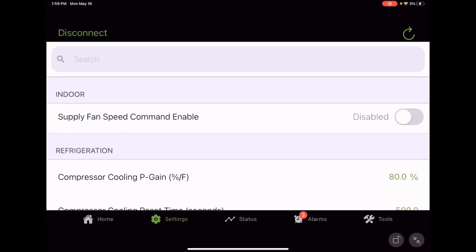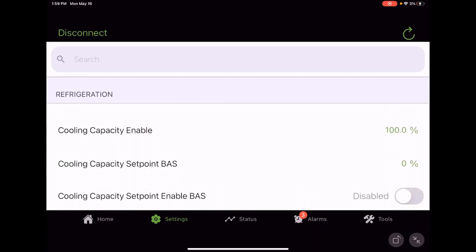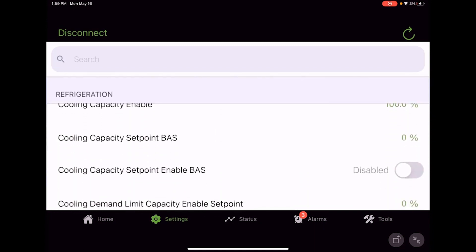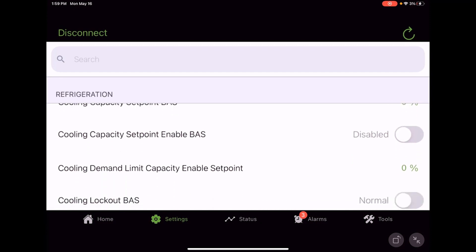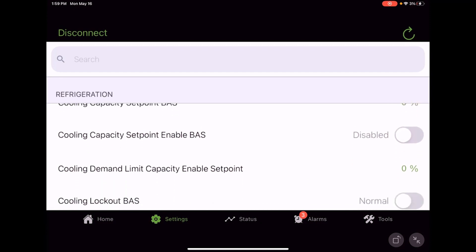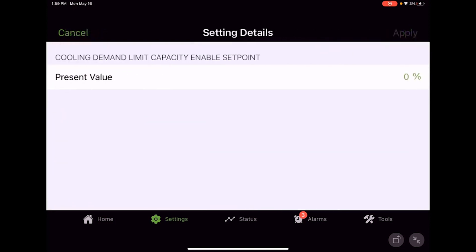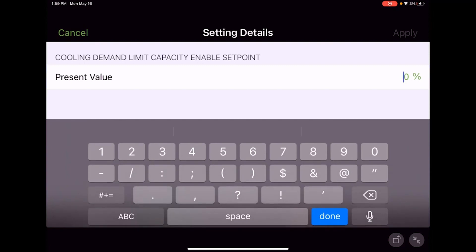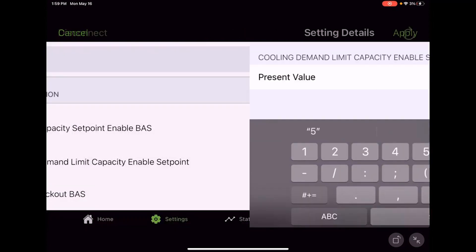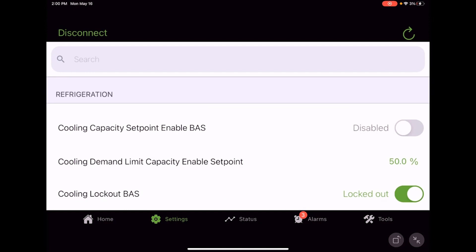We've got other settings here. We've got some things that have to do with cooling capacity demand limit. So if demand limit is triggered, we may want to demand limit that unit 50%, so we'll only allow 50% of the cooling to come on. Do we want to let the cooling lockout BAS be in effect or not? We can toggle that normal or locked out.